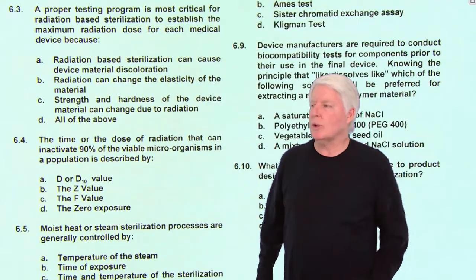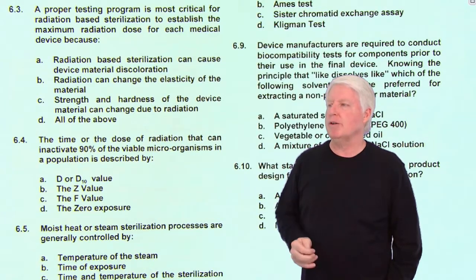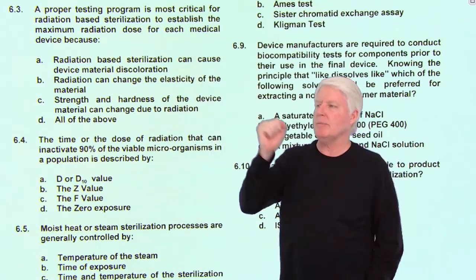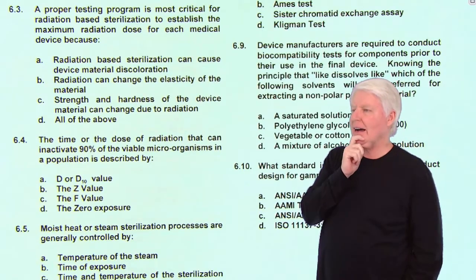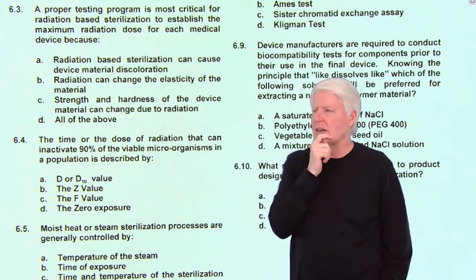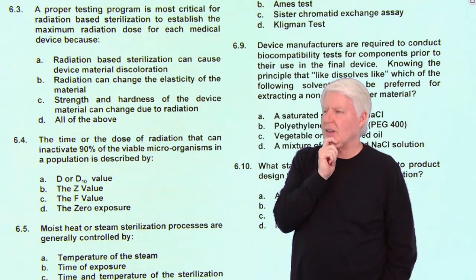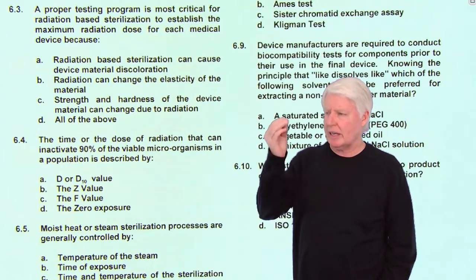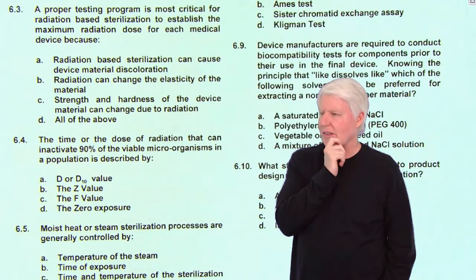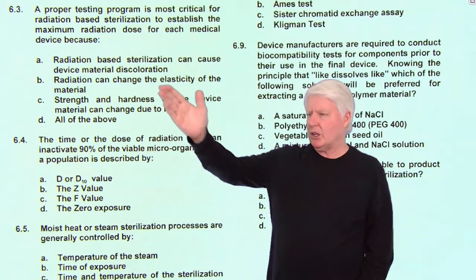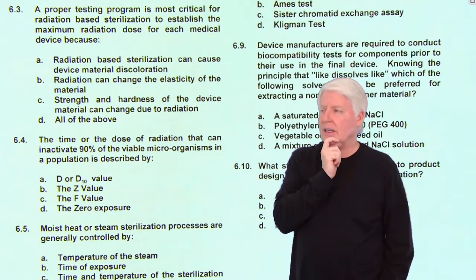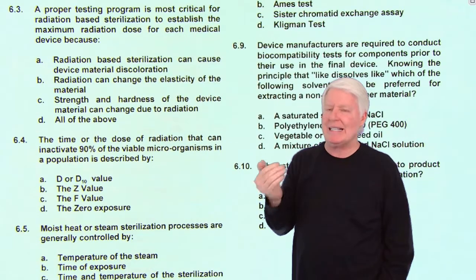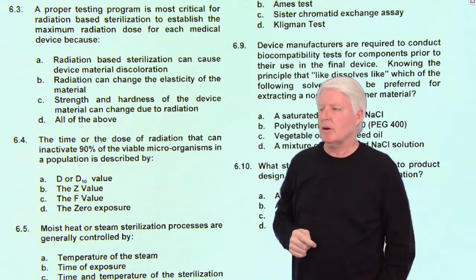Very good, here we are at question three. A proper testing program is most critical for radiation-based sterilization to establish the maximum radiation dose for each medical device, because radiation-based sterilization can cause device material discoloration. For certain materials it does, and there are tables you can look up to see which materials discolor more than others. Radiation can also change the elasticity of the material. Yes, it could, that's why radiation isn't the best sterilization process for all materials.